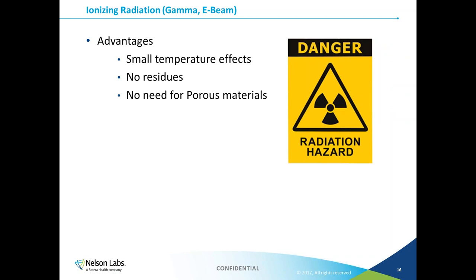Let's look at advantages and disadvantages of ionizing radiation. One primary consideration is that ionizing radiation has very little temperature effect on materials, making it much more compatible with heat-sensitive polymers. Because there are no chemicals involved, there are no residues to worry about in the traditional sense. However, since ionizing radiation can alter materials on the molecular level, chain scission — or cutting of molecules — could modify the material. Another great advantage is that there is no need for porous materials in the packaging, since electrons or gamma waves pass through packaging material easily — no breathability needed. This can lower packaging material price and also means that if a product is moisture-sensitive or sealed in a glass vial, the packaging can easily act as a moisture barrier while still allowing sterilization.